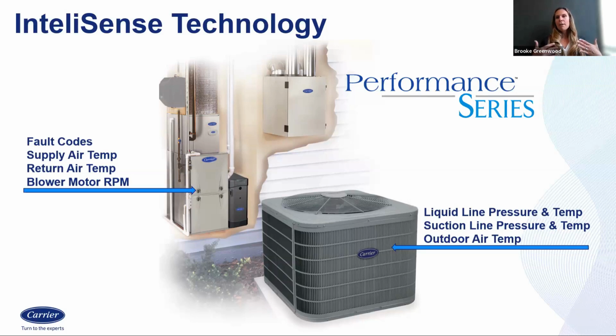But remember, since power isn't applied, you won't see live numbers. When you're out there troubleshooting though, you'll be able to see what your high and low were in heating and cooling from your air temperature sensors, and what your average was over that time period when it was running. So again, this gives you more information, more detail, more data to help you really diagnose and troubleshoot what's going on.